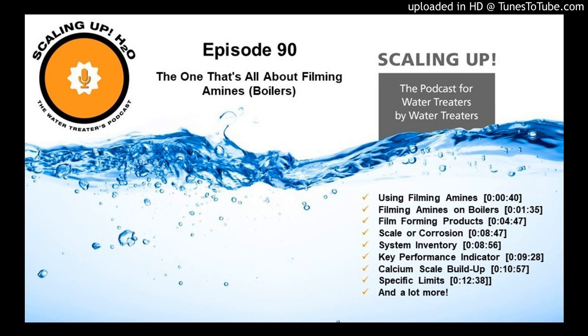And what we don't want to have happen is for all of that to move into a steam trap or a low flow area or an elbow, or pick something, and then just sit there, right? We don't want to move so much so fast that the rate of remobilization supersedes the rate that we can blow it down and get it out of a system. So that comes to the other point in our slow and low mantra, and that is blow it down, blow it down, blow it down. You've got to get it out of there.